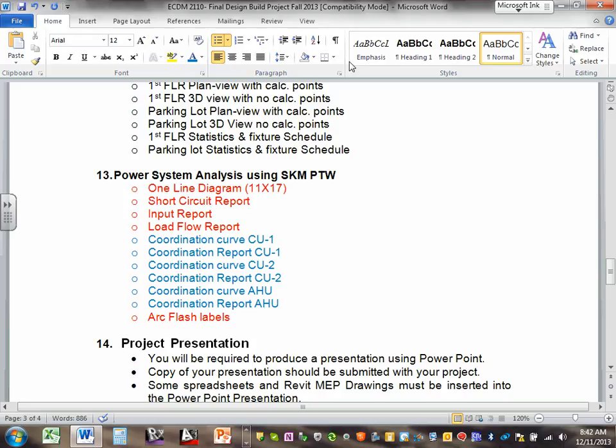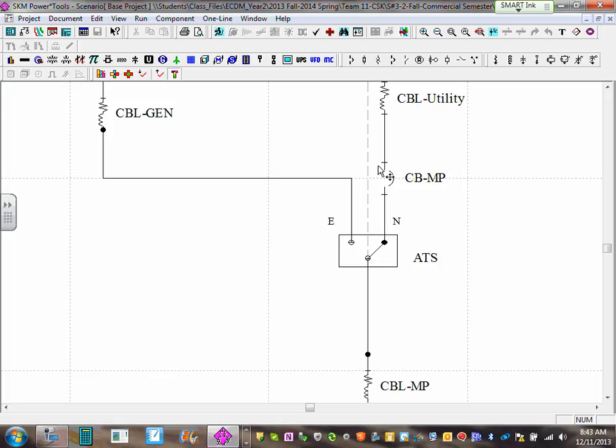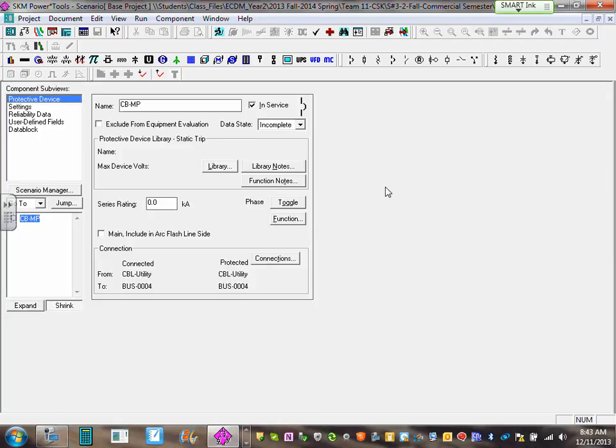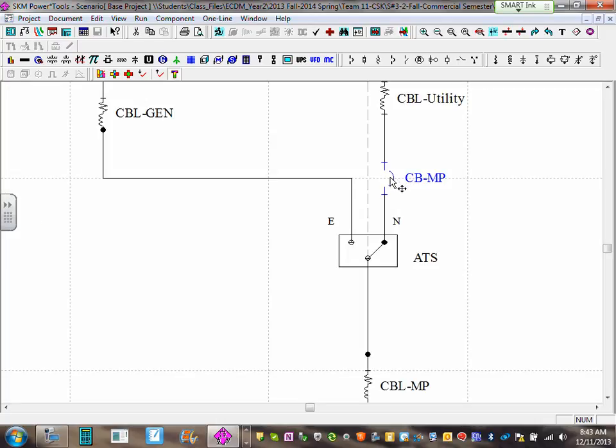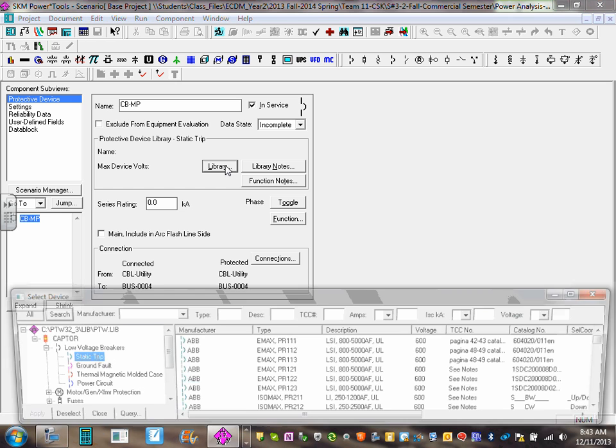To do the coordination, now that we've put the circuit breakers, I'm going to load them with information. Every manufacturer of every circuit breaker — low voltage, high voltage, or fuse — has a library inside the software. Remember the IES file we used for every fixture? There's an equivalent for every circuit breaker. Go to the main circuit breaker, zoom in, and double-click on the icon to open the component editor.